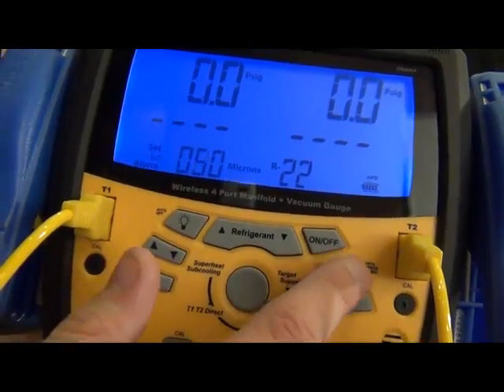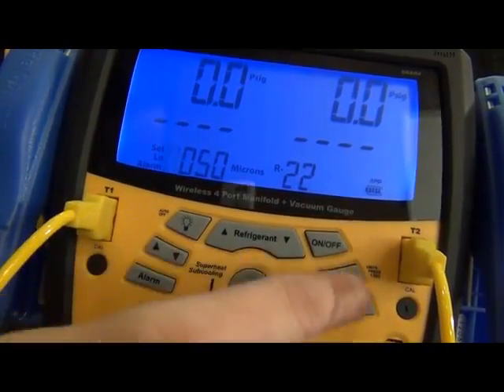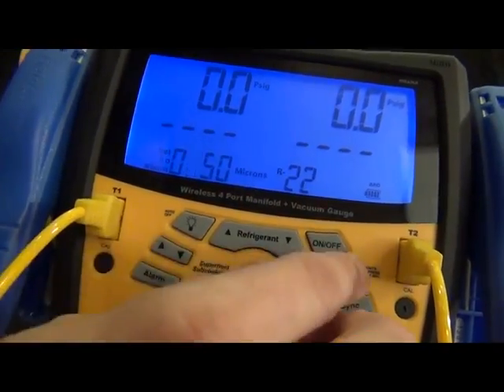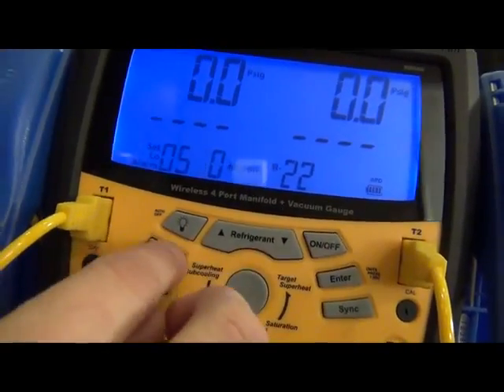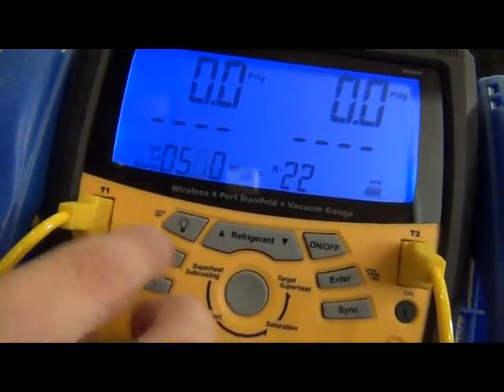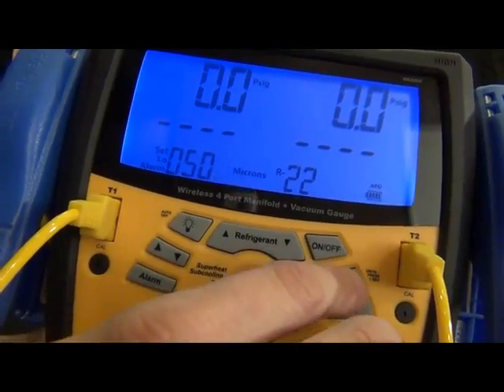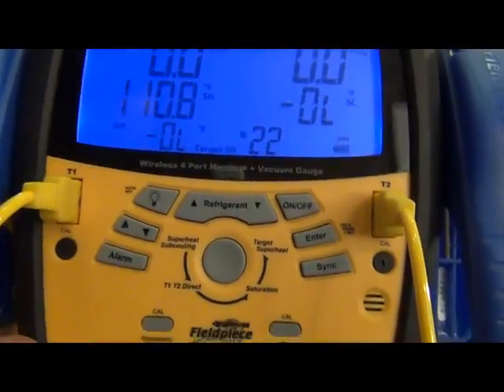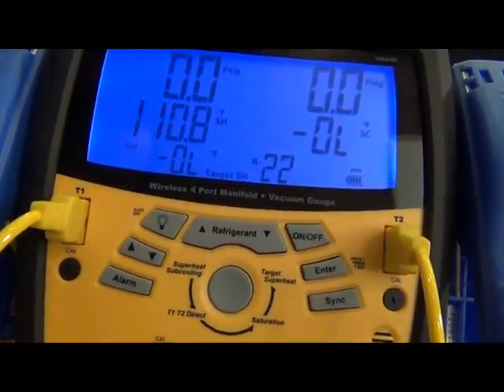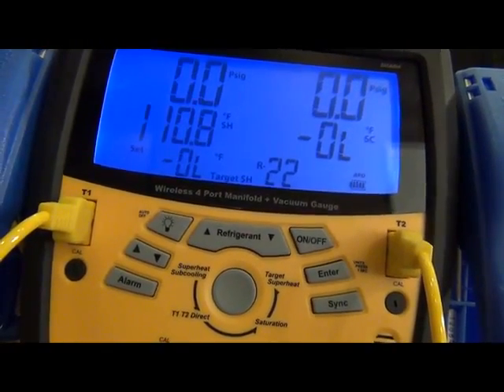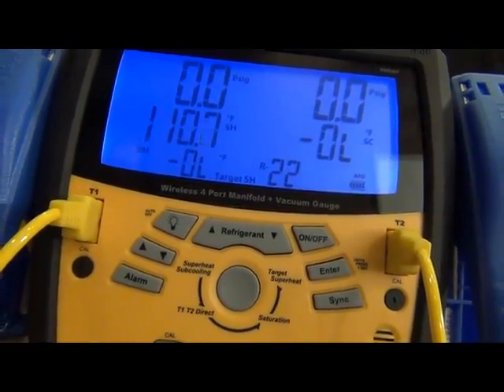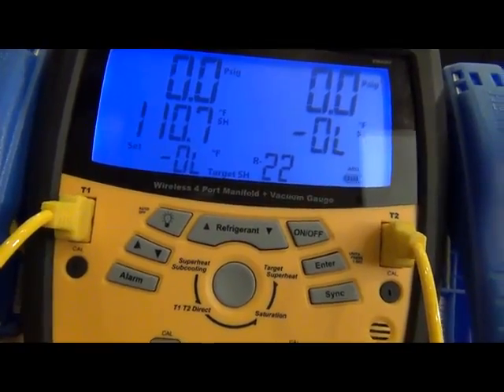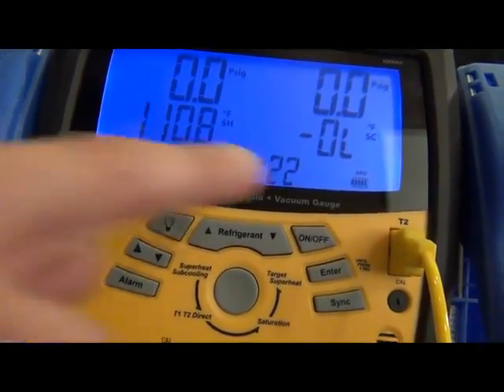the alarm will go off at a thousand microns. So now your low microns, you might want to set it for something like 500. And now what it'll do is when I start pulling a vacuum, you'll see the first alarm go off when you hit 500 microns. That's the low level. And then as you turn off the pump and shut down the system, the microns start creeping up again, and it'll go off once it hits a thousand.